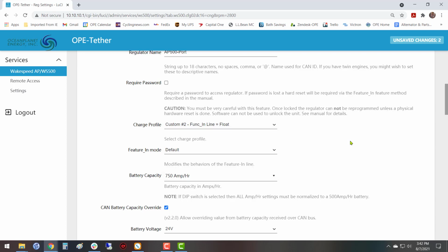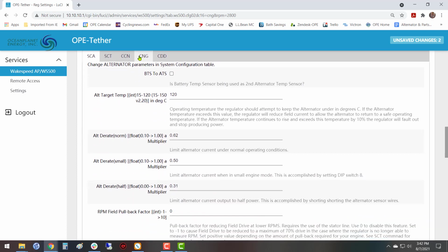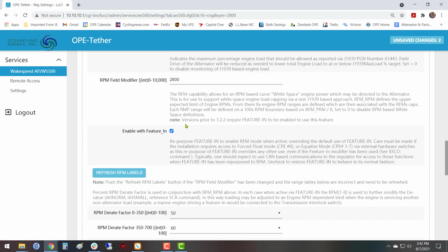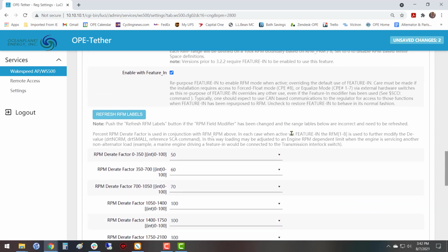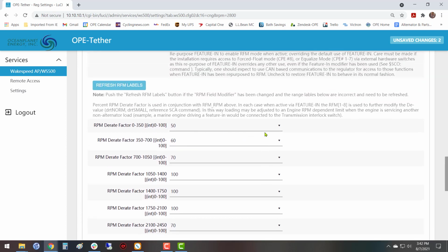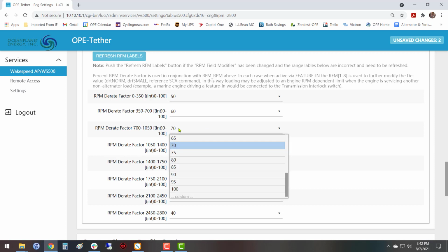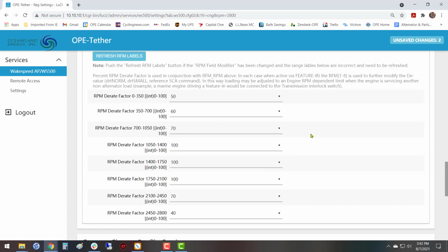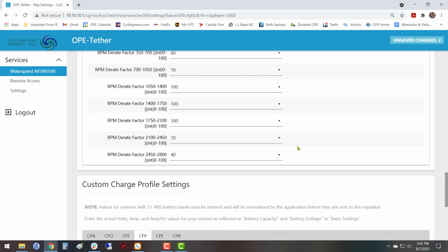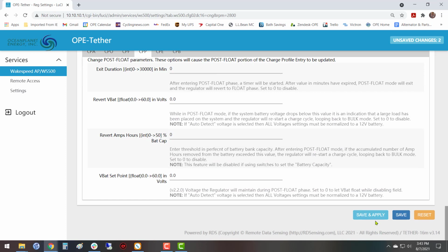It's the same wire. It's just one of the wires that allows you to turn some functions on and off. But what we do on this tab is that we make it so that when there is voltage on that wire, it is in the curve mode here, the loading curve mode. If you take voltage off the wire, then it'll go back to generator mode, which means you would get full power here instead of 70%, if you so desired. Some people just leave it on all the time. Okay, so let's hit save and apply.